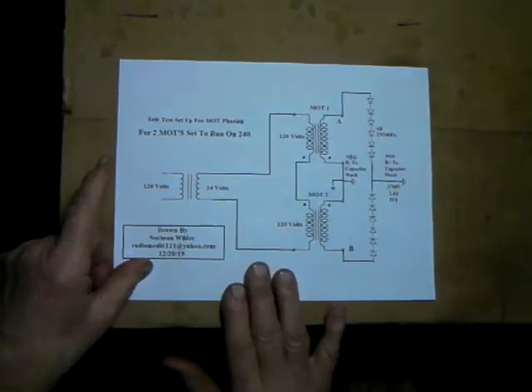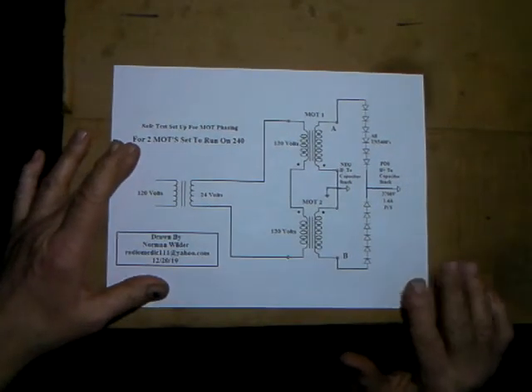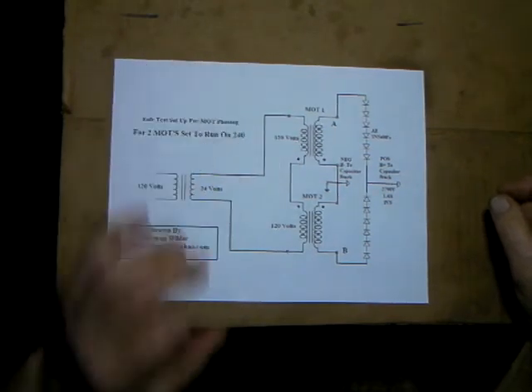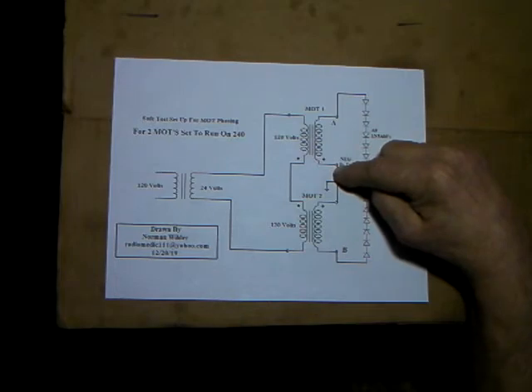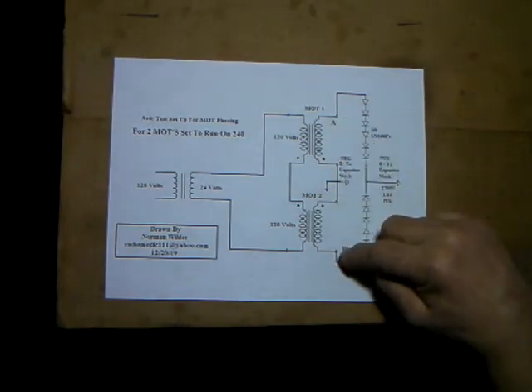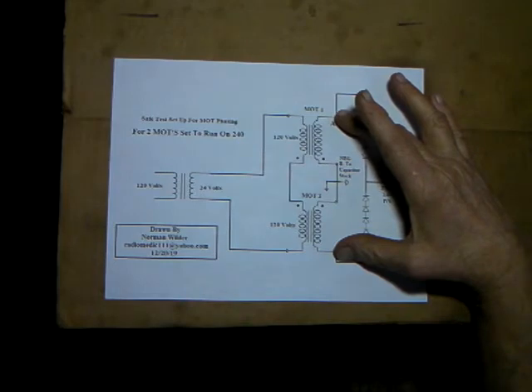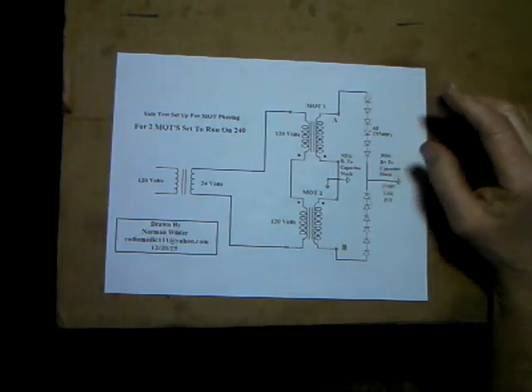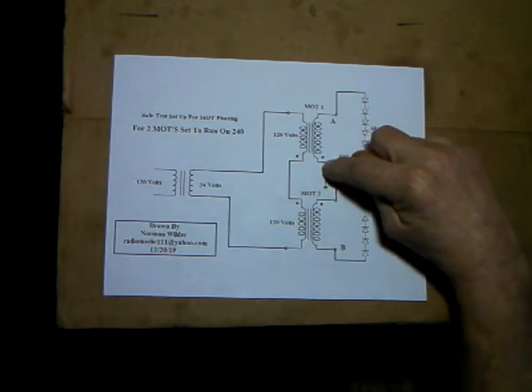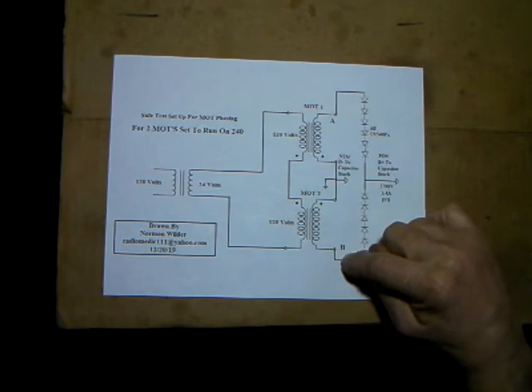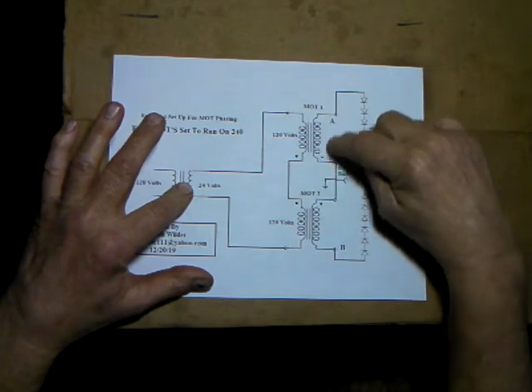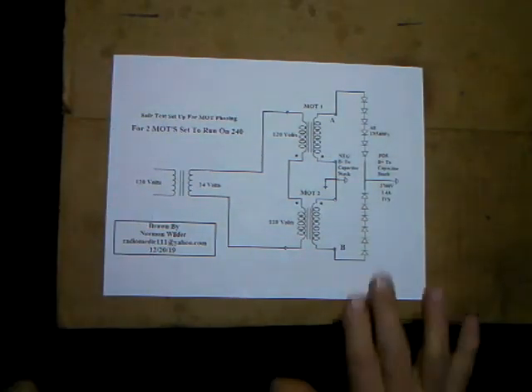Okay, and the safe way to test your 240 volt setup, same idea. You keep in mind a times 10, so you'd use a 24 volt transformer. Hook it across the two transformers in series, 24 volts. You measure the voltage from here to here, will be for one transformer. And on this one, if you measure from here to here, you should see twice that voltage, if you have these windings hooked up correctly. If you don't, you just need to swap one of these. That's the idea, is you need to see twice the voltage here, that you see from point A, to the ground terminal of that one. So, from outside to outside, using a 24 volt transformer, this should measure twice what you see from here to here.